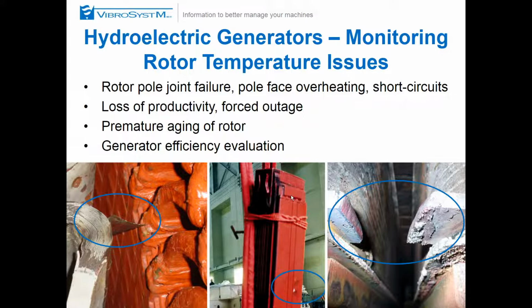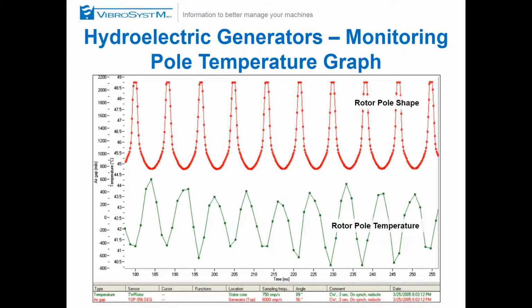And in this case here, we could see that the pole was so hot, there's actually some blistering occurring. At the bottom, you can see where the paint's coming off. So it was so hot that the paint's coming off the pole. Okay. And you have an indication here, in red, the air gap is showing you the pole shapes, and in green, you can see the temperature that is measured by the probe.